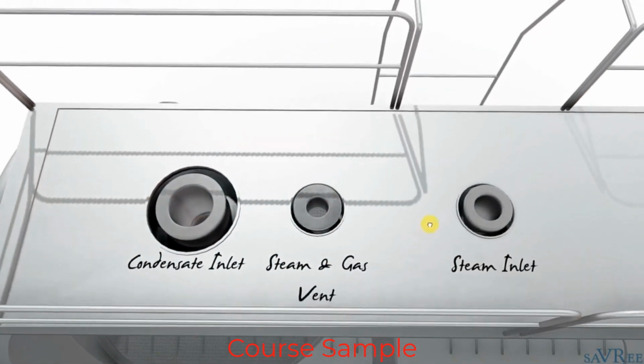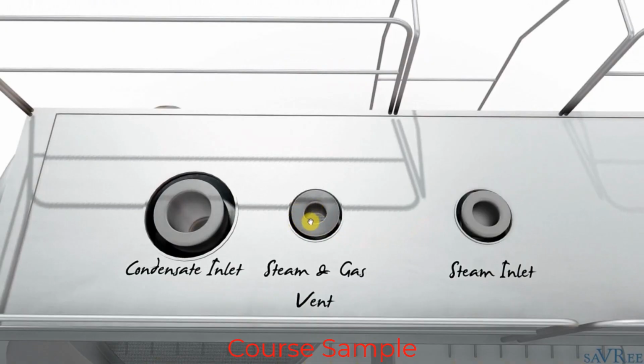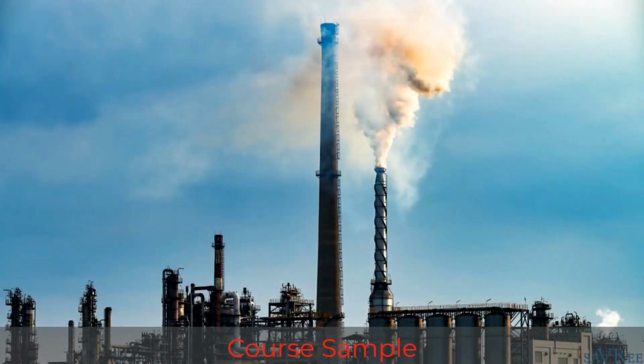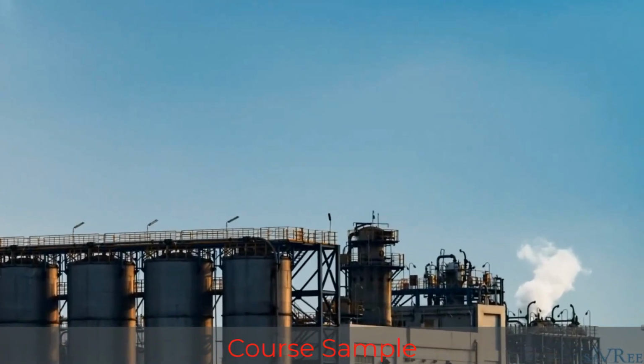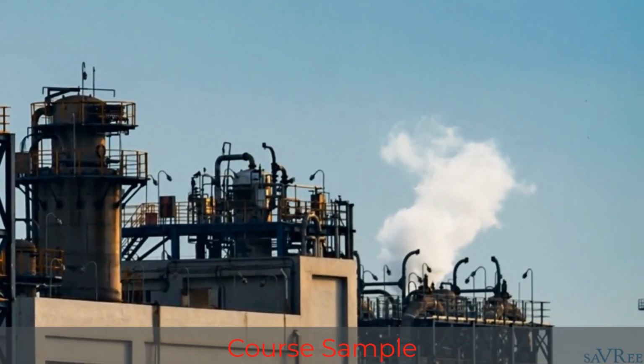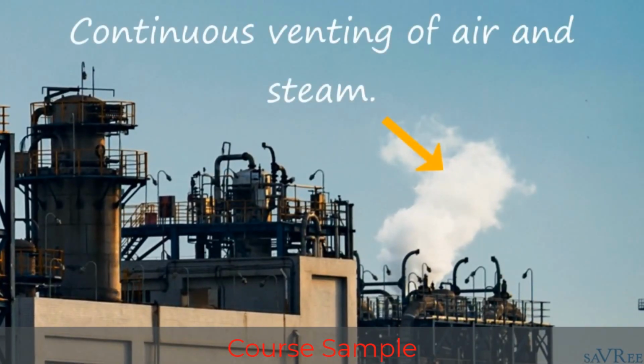We have a steam and a gas vent, that is this connection here. Although the deaerator is under a very low pressure, as I mentioned before, about 0.5 bar or 7 psi, sometimes a little lower than that, we actually have a vent that vents to atmosphere continuously. It's not possible to separate the non-condensable gases from the steam in an efficient manner. So what we do is we actually allow a bit of the steam to escape with the non-condensable gases. For this reason, you'll often see a little bit of steam always escaping the deaerator vent.